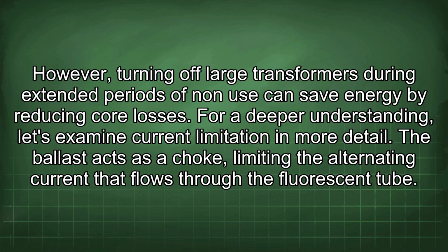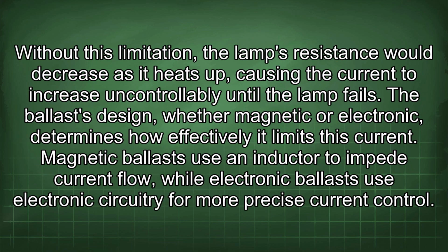For a deeper understanding, let's examine current limitation in more detail. The ballast acts as a choke, limiting the alternating current that flows through the fluorescent tube. Without this limitation, the lamp's resistance would decrease as it heats up, causing the current to increase uncontrollably until the lamp fails. The ballast design, whether magnetic or electronic, determines how effectively it limits this current. Magnetic ballasts use an inductor to impede current flow, while electronic ballasts use electronic circuitry for more precise current control.